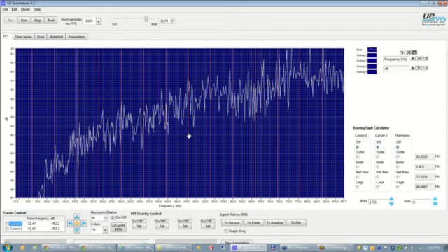With the electrical type faults, and specifically we'll refer to tracking and arcing, we will see a couple of 60 hertz fault frequencies, and then they will drop off of the spectrum as we move out further to the right here toward the 900 setting that I have on this particular display.